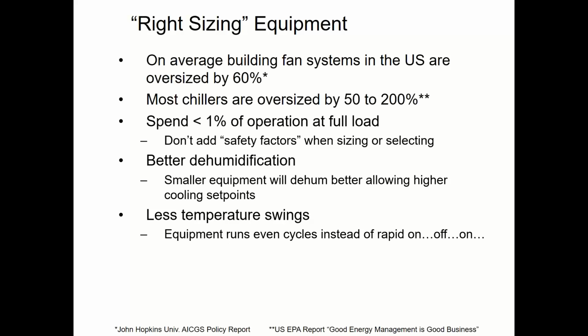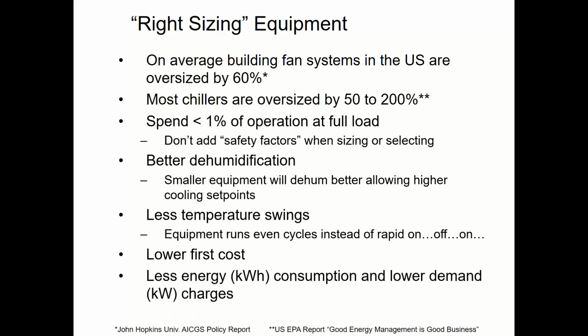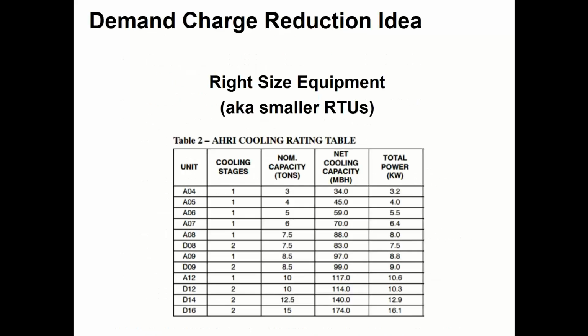I used to say downsize equipment, but now I call it right sizing because when I say downsizing, people would freak out. I don't want you to size it below what it's supposed to be. I want you just to finally do it for once the way it's supposed to be instead of oversizing it. So less temperature swings, less wear and tear on the equipment, less on and off cycling. It costs less to buy smaller equipment. It saves kilowatt hours and it saves demand charges. Like everything's a positive. There's no negative to sizing it smaller. Not smaller than what you need, smaller than what you think you need.